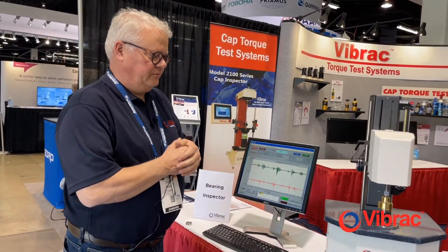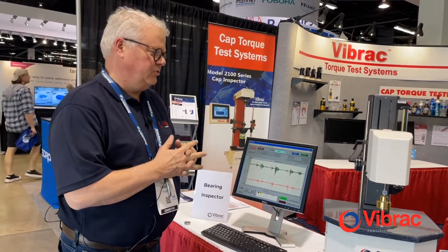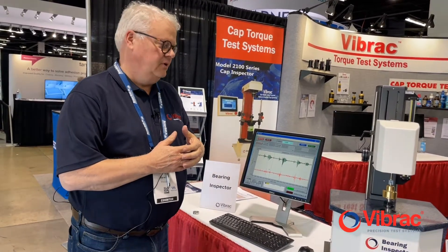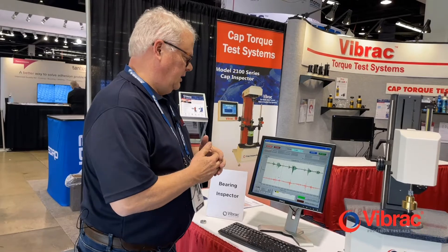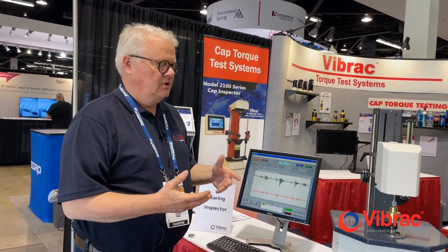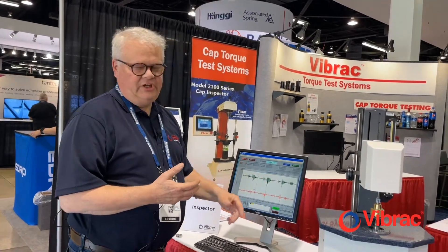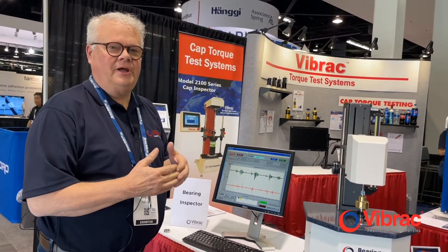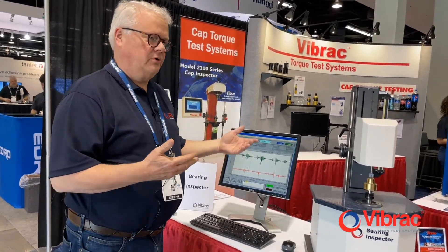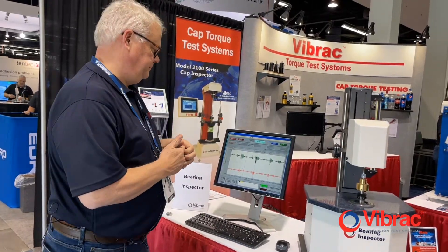We sell and manufacture these systems for companies like NASA, the Jet Propulsion Laboratory, and bearing manufacturers like Timken, SKF, Barden, and Schaeffler. They use these slow speed tests — rotating at one RPM — for the resolution needed to see what kinds of issues there might be with a bearing before it's installed in a critical system or a high sensitivity rotational application.